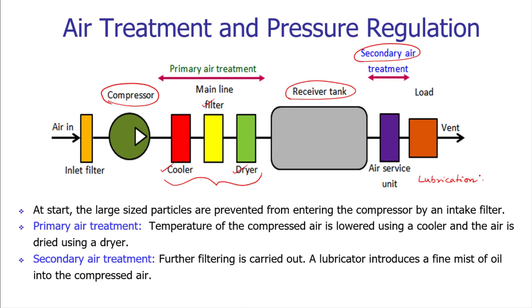At the start of the compressor itself, we use a filter to remove large size particles and protect the compressor. In the primary air treatment stage, temperature must be controlled — pressures increase very high inside the compressor, causing temperature to rise as well. So we need to cool down the compressed air. During cooling, there will be condensation of water vapors inside the air, which must be filtered out. For that purpose we need a dryer, and then the air is stored in the receiver tank.